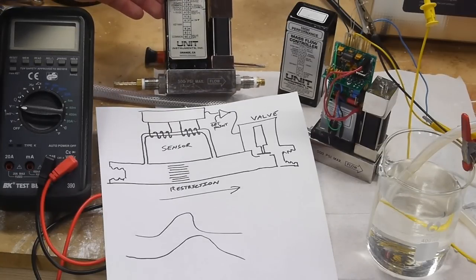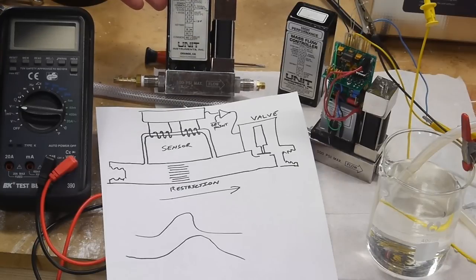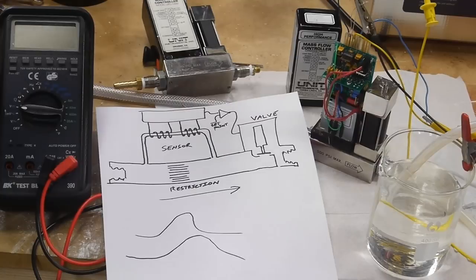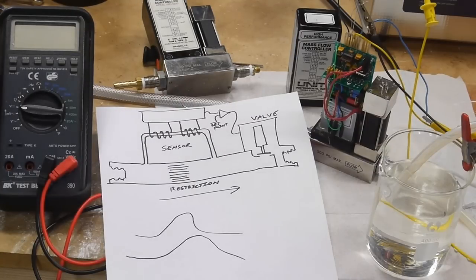This unit is calibrated for a hundred standard cubic centimeters per minute of argon and this valve that I have hooked up is 10 cubic centimeters of oxygen per minute.